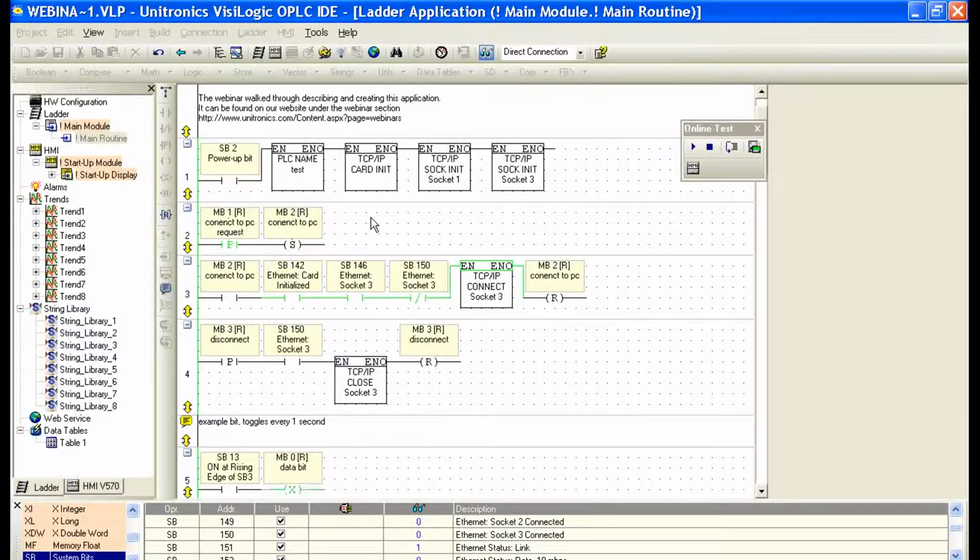Modbus, for example, if we have an event that says read from controller 2, but we currently are in the middle of a Modbus read, maybe from controller 3, if we simply use a positive transition in the read command, we'll miss it. The system will be busy and we won't actually send. So what this is doing is setting a bit, and it's waiting for the first opportunity it sees to perform that command. In this case, it's a TCP/IP connect.